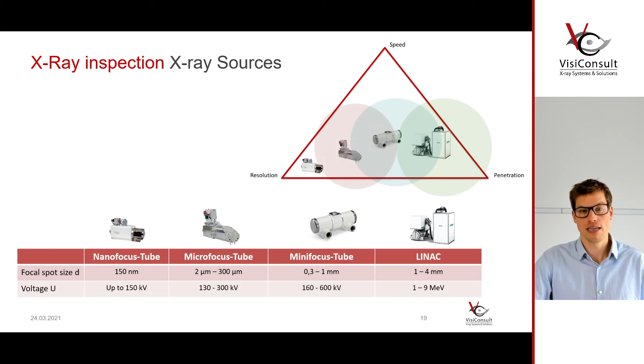So what is important, and this is the big takeaway, you have a triangle here between resolution, speed, and penetration. You can't have it everywhere. If you want high resolution, you cannot scan big parts. If you want high resolution, you cannot scan parts fast. If you want to scan big parts, forget about speed, forget about resolution. And your quality engineers are moving in that spectrum. And I will come back to this later, why this is so important to keep in mind. CT quality inspection is not a miracle tool. It has physical limitations, and you have to keep them in account to design parts that actually are inspectable by your colleagues.